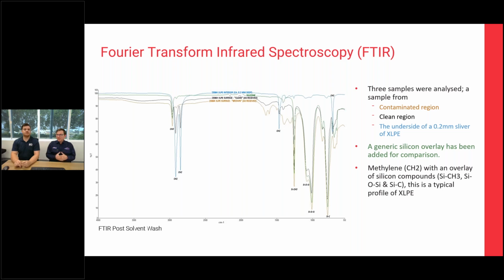So getting more into the complexity of the investigation, Fourier transform infrared spectrometry is an analysis technique that identifies chemical components across the insulation medium, and specifically we're looking at the XLPE. Three main samples were taken: the contaminated region, so the area of dark pollution, the clean region, and then we took a small sliver of XLPE off the cable at 0.2 millimeters thick, and measured the underside of that. That was to see what had penetrated the surface of the XLPE. We can see a generic overlay of silicon on the profiles that we're looking at, and that can be expected from the silicon oil embedded in the termination.